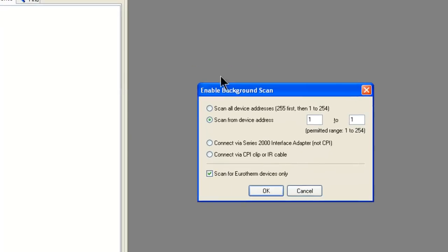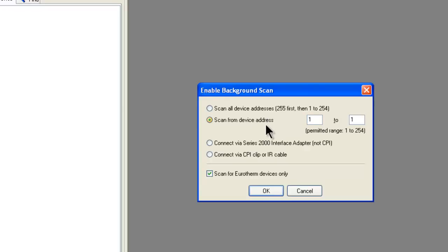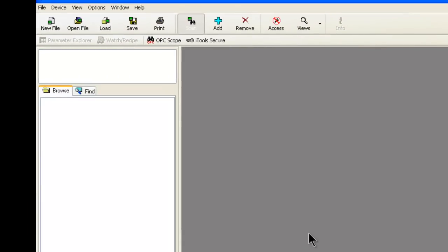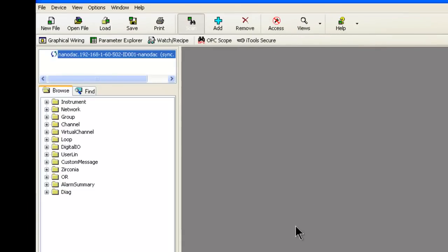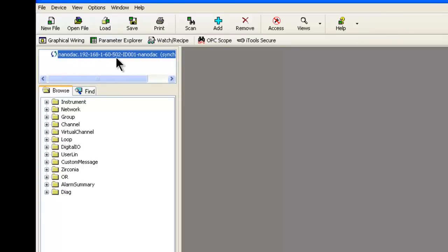If everything is successful, we will scan from address one to one with the radio button checked for scan device address. If everything goes well, it will find the recorder on our network, and there it is. Notice NanoDAC 192.168.1.60, port 502, ID 01, and it is synchronizing.